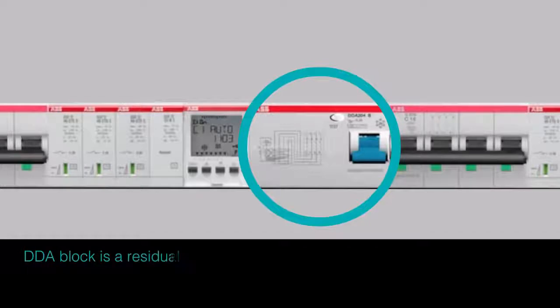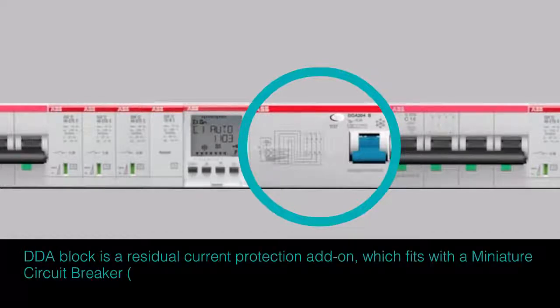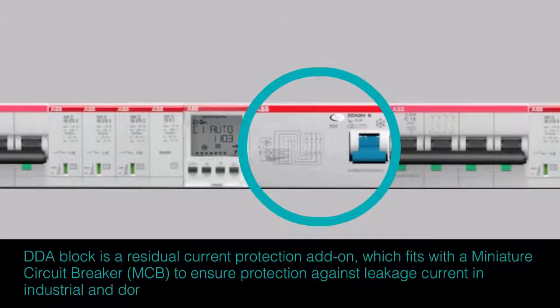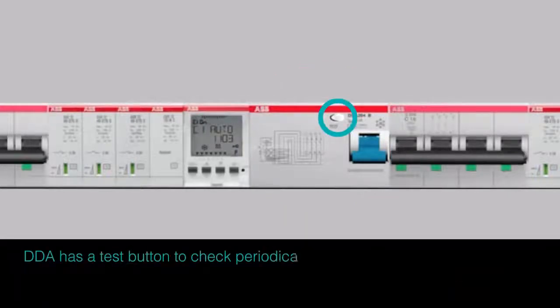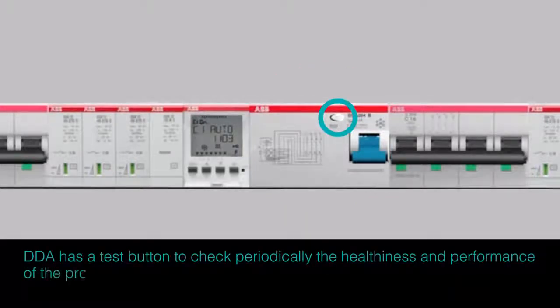DDA block is a residual current protection add-on which fits with a miniature circuit breaker, MCB, to ensure protection against leakage current in industrial and domestic applications. DDA has a test button to check periodically the healthiness and performance of the product.